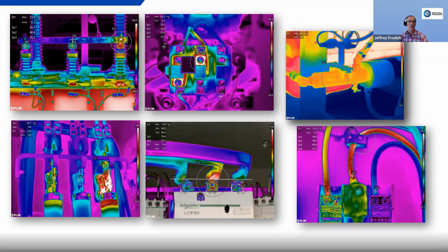In the top center, you've got a motor starter overload. That contact on that B phase has gone bad and needs to be cleaned up, and possibly it's an aged piece of equipment, so you may have some interior issues going on there where it might even need to be replaced, but clean and tighten. On the top right, you actually have a normally operating engine block heater. Sometimes we're checking for heat that's supposed to be there to allow the fuel to be properly heated up so that the engine can start properly. So it's a check. If it's cold in this case, that's a problem, and we're going to identify that.